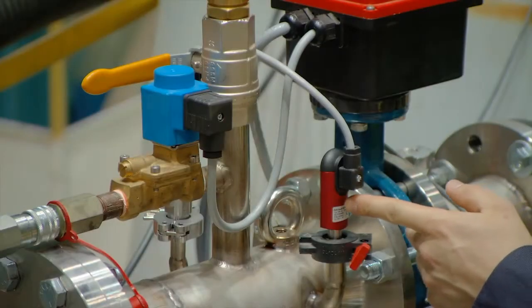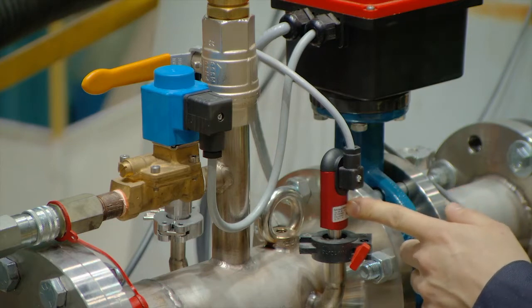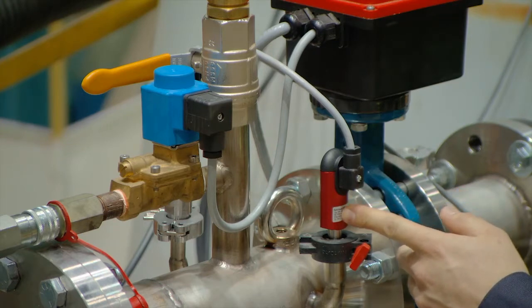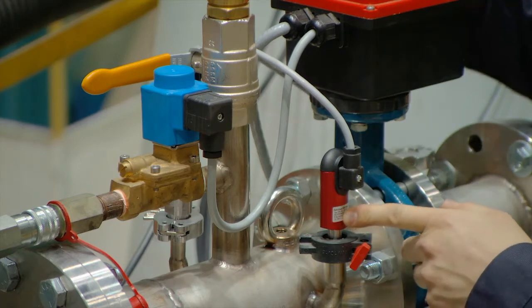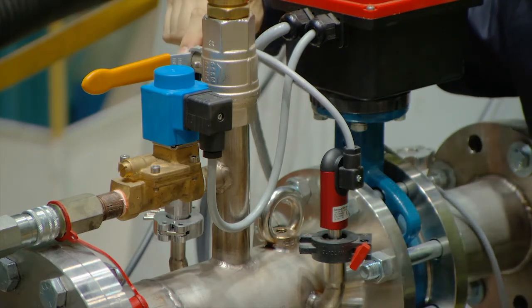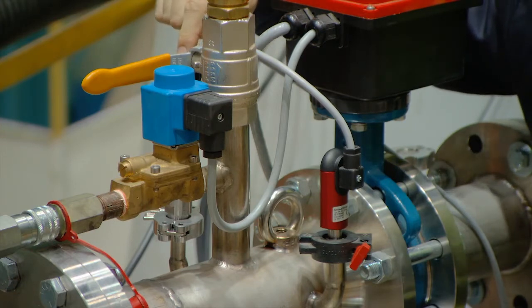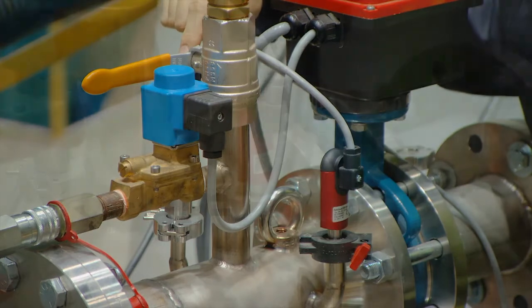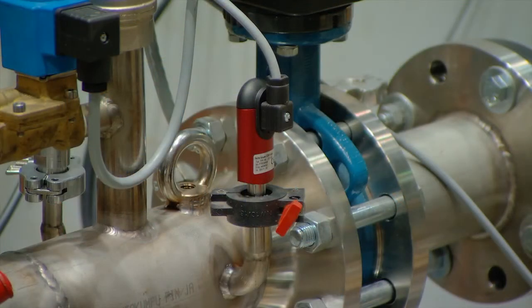This right here is a Pirani vacuum gauge. It's the fine vacuum gauge, so to speak. It is accurate between 0 and 10 millibar. On the back side of the valve assembly is the WIKA pressure gauge. This is the coarse vacuum sensor. It is accurate between 10 and 1000 millibar. In regards to the Pirani gauge, since it is a very sensitive instrument, it only goes between 0 and 10 millibar. While installing it, you do require an insulated gasket as well as an insulated clamp on it in order for it to function properly. And you will notice fluctuations in the vacuum readings while you're injecting current into the transformer. That's one telltale sign that it's not being insulated properly.